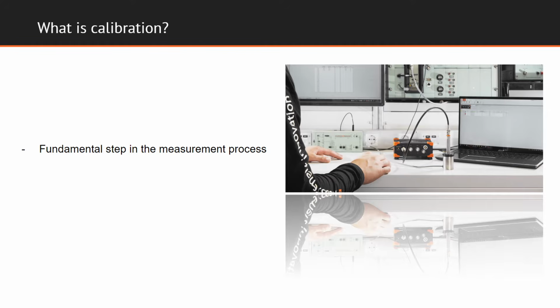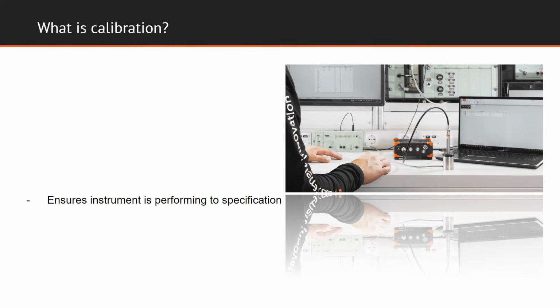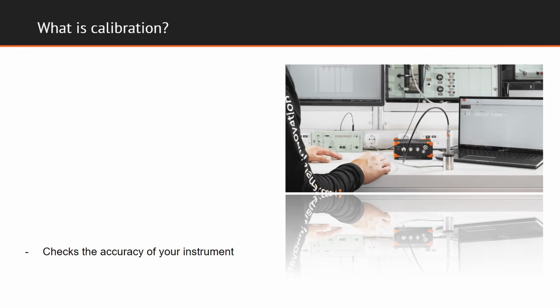each measurement instrument must be calibrated in order to know that the readings of the instruments are indeed true. So consequently, calibration represents a fundamental step in the process of measuring. And why is that so, one might ask himself? Because calibration ensures that your instrument accurately indicates the required measurement parameter and also that it's performing to specification. In essence, calibration checks the accuracy of your instrument and also determines the traceability of your measurement.